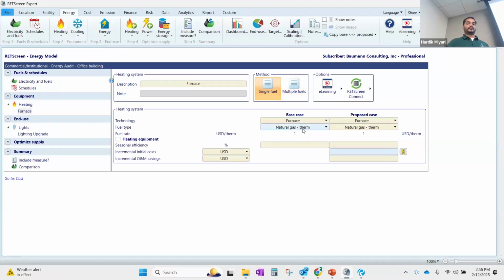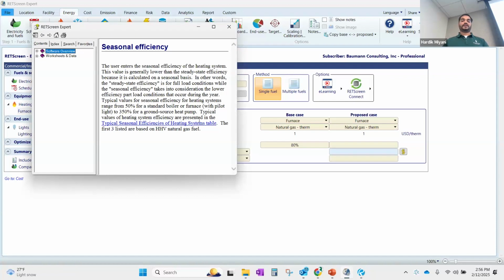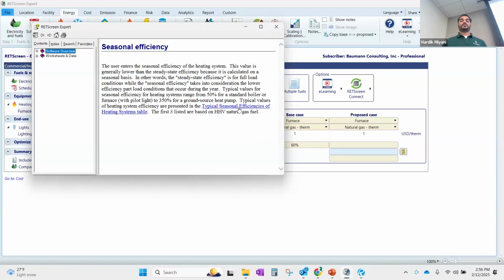Now, suppose you go on an energy audit and you don't have this information - this is something we see many times. If you go into an old building, they don't have drawings, the building engineer doesn't know what the efficiency is, or they don't have a nameplate picture. So how do we estimate? RETScreen has a very good database - if you select the seasonal efficiency, that's a place where they've given a reference you can use.